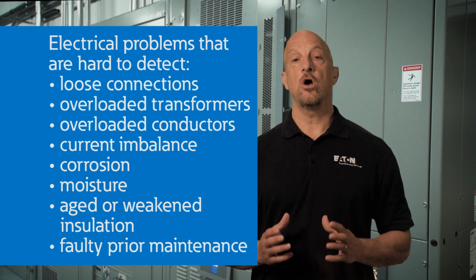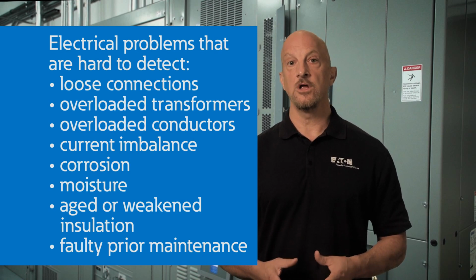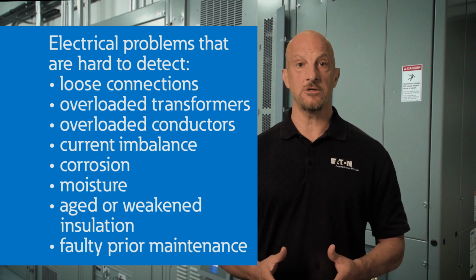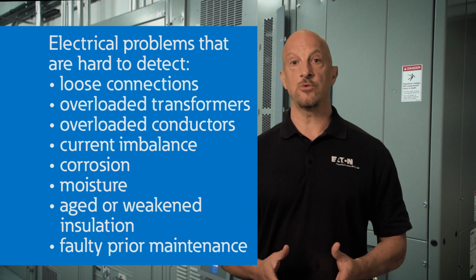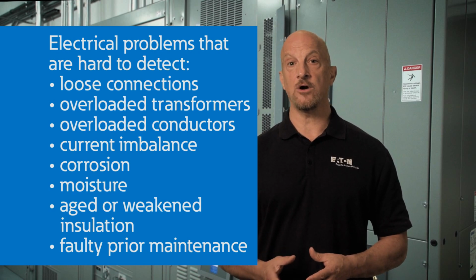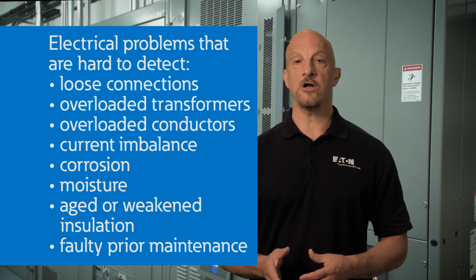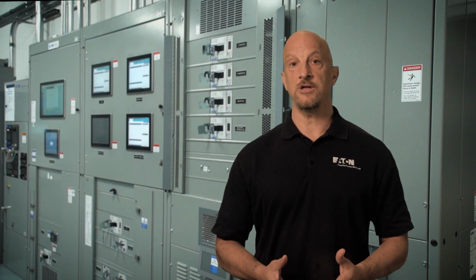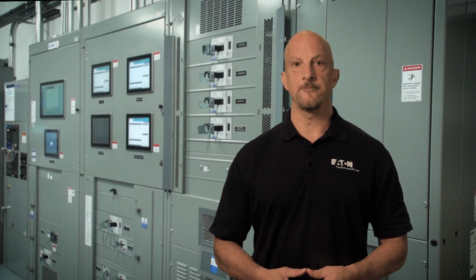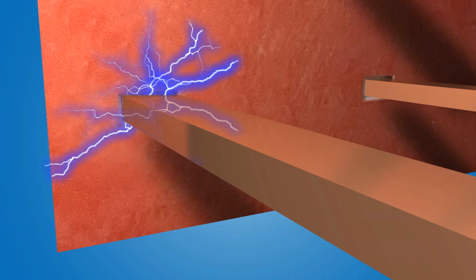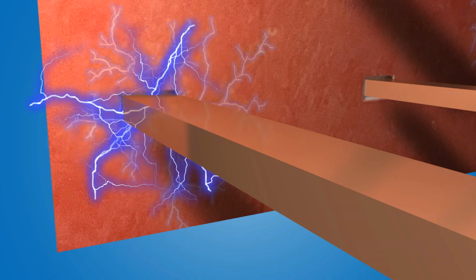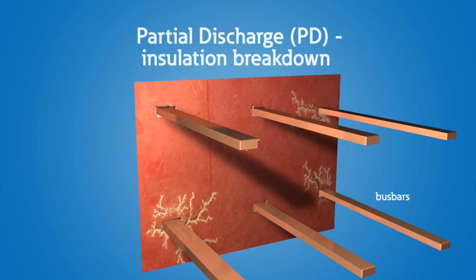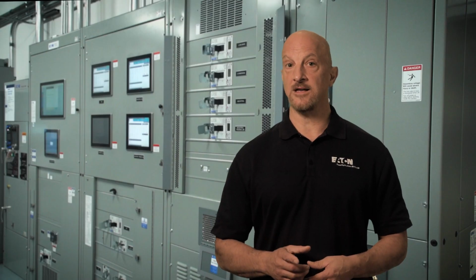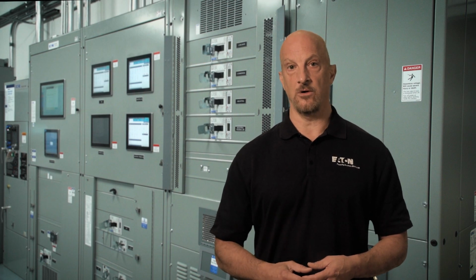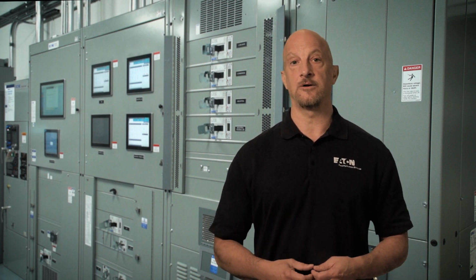Loose connections, overloaded transformers or conductors, current imbalance issues, corrosion, moisture ingress, aged or weakened insulation, and faulty prior maintenance procedures are all documented causes of electrical fault conditions which can generate heat. And some failure causes, like partial discharge, will not result in a temperature rise as a warning before failing the equipment. These failure modes are in fact discoverable prior to a fault, and I'll discuss this a little bit later.